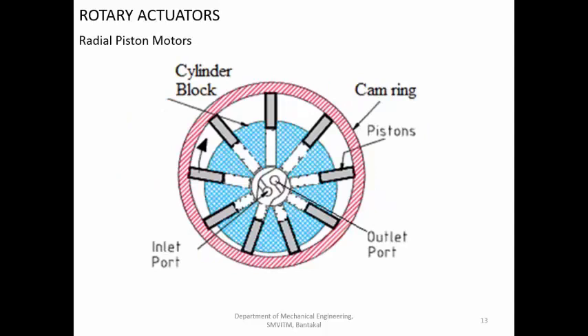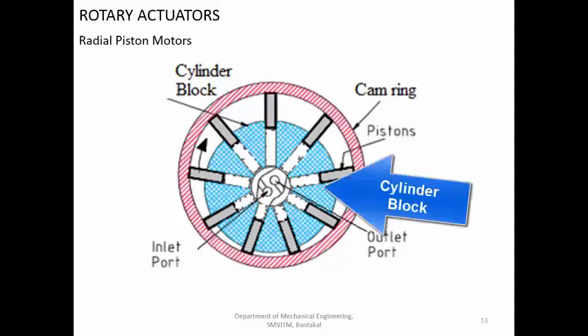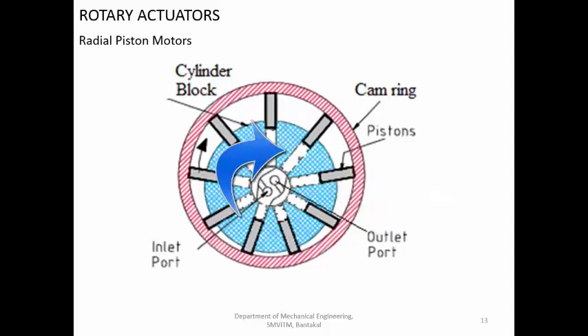Next one is the radial piston motor. In the radial piston motor, you are having the piston which is reciprocating inside. You are having the inlet port and the outlet port. Whenever high pressure fluid or compressed air enters, the pistons are pushed outward. The forces will be tangential and perpendicular to the inner surface. Because of the tangential component of the force, this cylinder block will try to rotate. When the cylinder block rotates, the drive shaft connected to it also rotates and a rotary motion is generated.